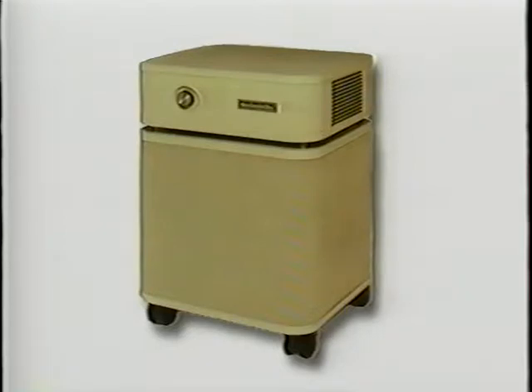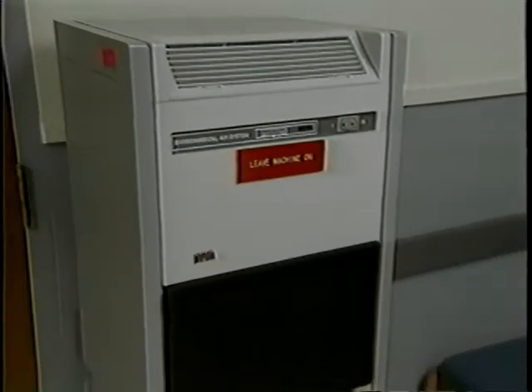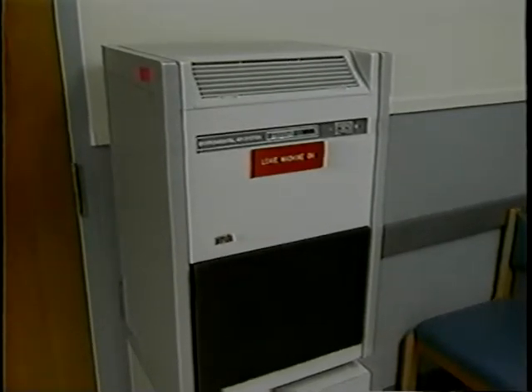These units come in a number of different configurations. The most common are small portable units that can produce 100 to 400 CFM. The larger portable units are rated for 150 to 800 CFM. Other designs include ceiling-mounted and wall-mounted units. The actual amount of air produced by these units is difficult to measure compared to a ceiling or wall outlet because you can't just put a flow hood up against them. Also, they may produce less air than the nameplate lists. We recommend that you size them to produce about 25% more capacity than you want.